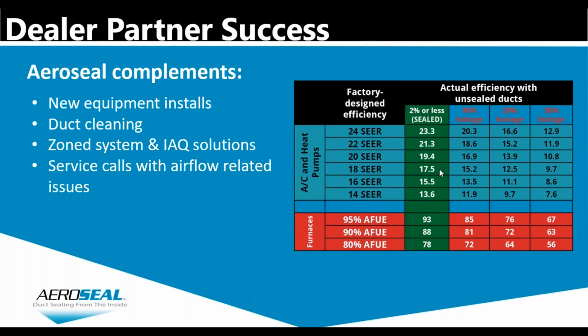Okay, so to sum this up, what dealers are finding is they can actually provide homeowners with greater efficiencies at a lower cost. So a typical scenario might be this. They may currently be installing an 18 SEER system for say $14,000 without Aeroseal. And that's going to deliver an effective SEER rating between 12.5 and 9.7 SEER, okay?